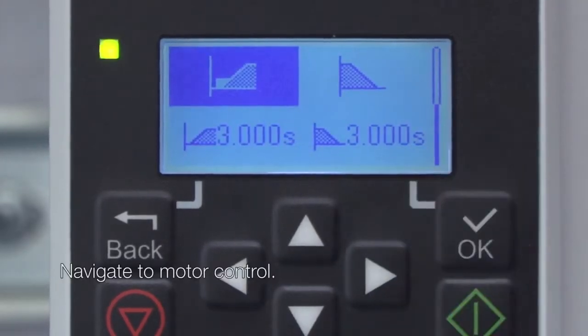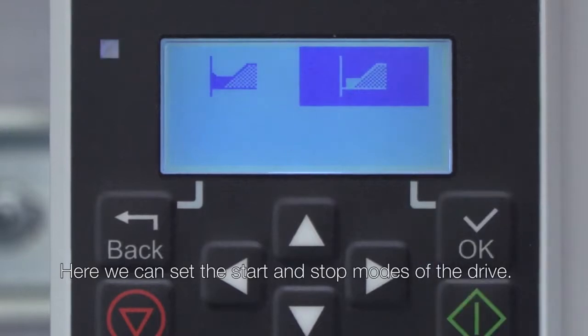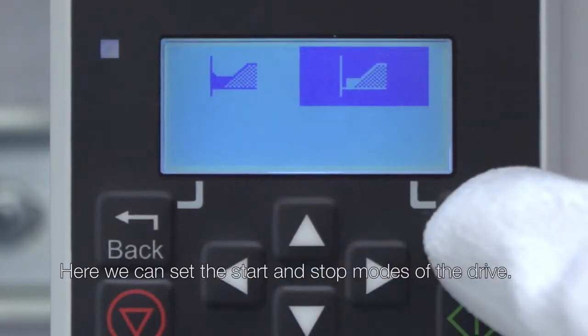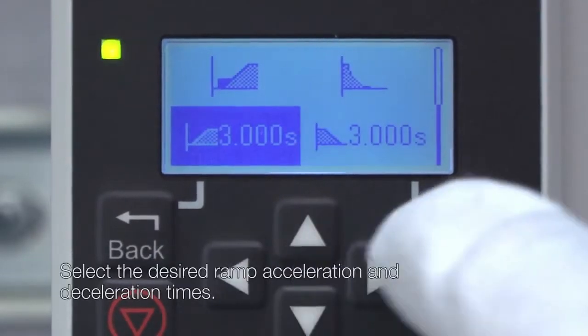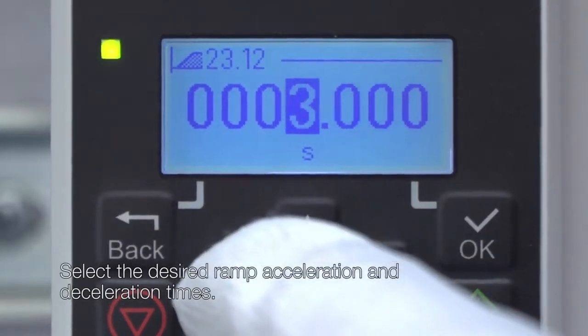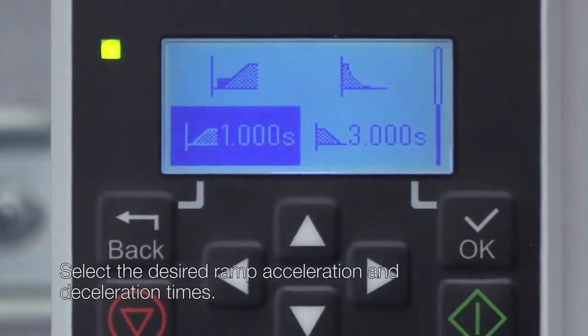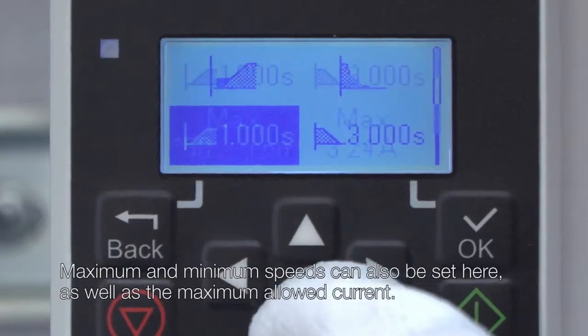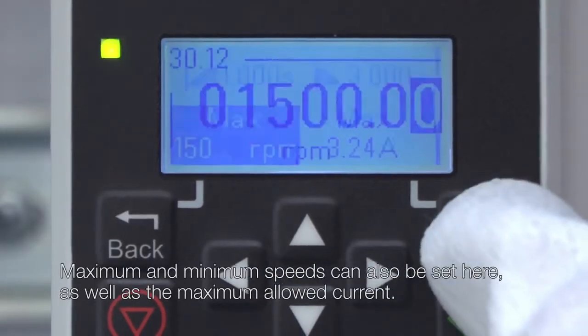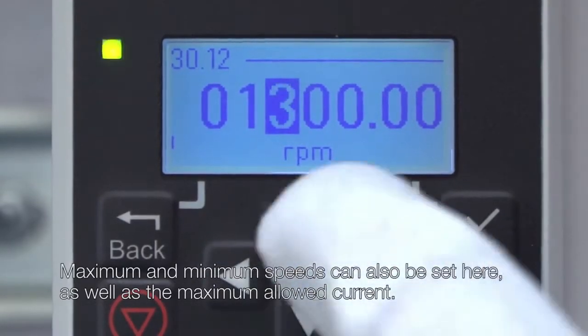Navigate to Motor Control. Here we can set the start and stop modes of the drive. Select the desired ramp acceleration and deceleration times. Maximum and minimum speeds can also be set here, as well as the maximum allowed current.